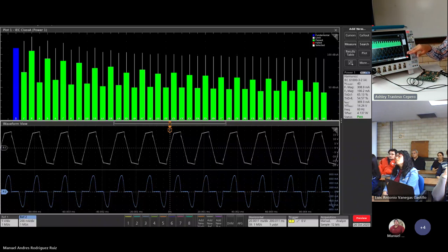Then taking the current waveform, try to calculate which are the harmonics, more for power measurements, and where is the fundamental, which are all the harmonics, and at the end, based on a specification, does it cover or not, pass or fail, and a standard for compliance testing.